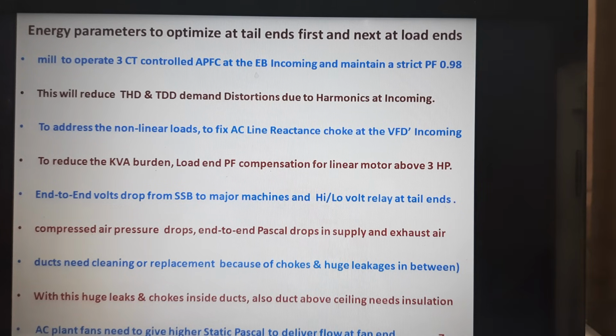The compressed air drops also: many of the mills lose more pressure, by more than a kg, at the compressor house itself, at the dryer. End to end, around 0.3 kg is normally the allowed norm. Let us try to reduce the pressure drops across the dryer, across the compressor, from the compressor to the mill.